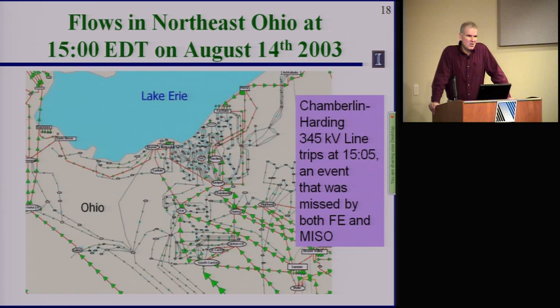Well, then the Chamberlin-Harding line tripped. There were 4 main 345s coming into First Energy from the south, and Chamberlin-Harding was one of those. That line tripped, which would be a significant event. The difference on August 14th is First Energy did not see it and MISO did not see it. That's extremely unusual. Utilities don't miss 345 kV lines tripping, but they did.